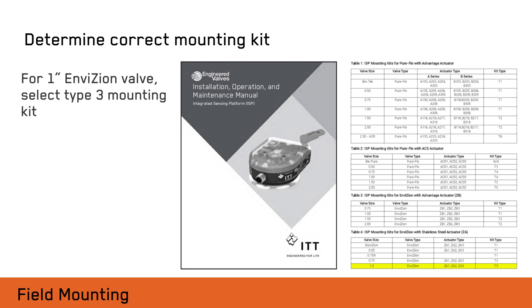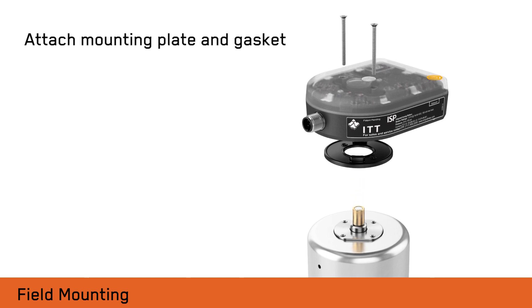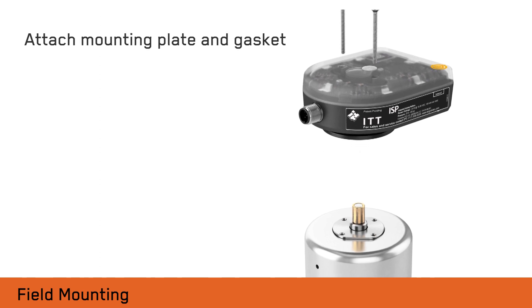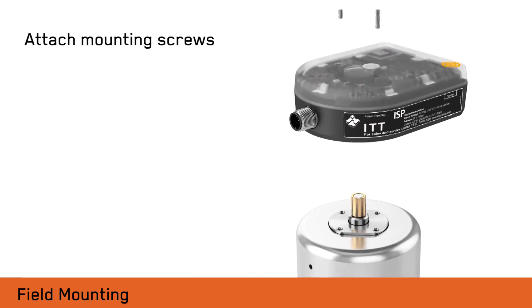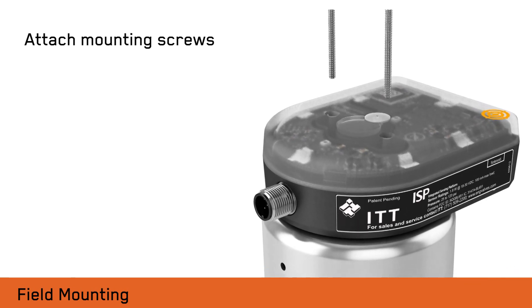The following instructions will illustrate a one-inch EnviZion valve with a stainless steel actuator. Install the sensing target magnet to the valve indicating spindle as shown. Insert the gasket into the bottom of the ISP. Attach two mounting screws through the ISP to the actuator mounting holes and tighten screws securely. The ISP is now mounted and ready for use.